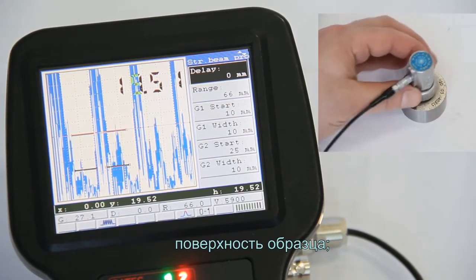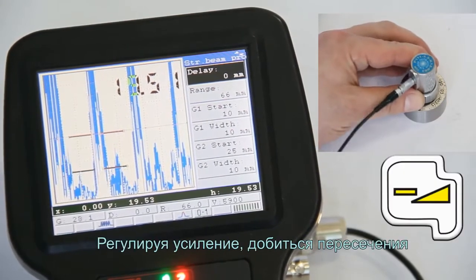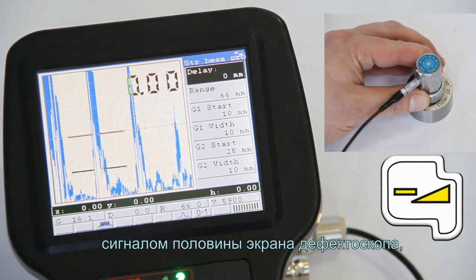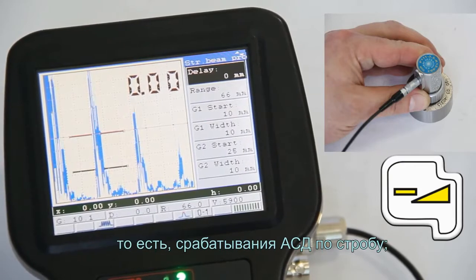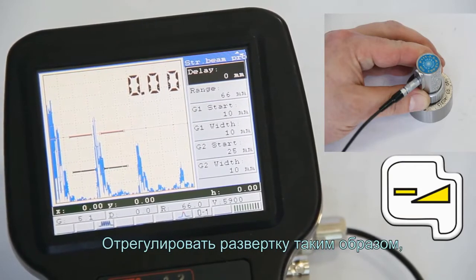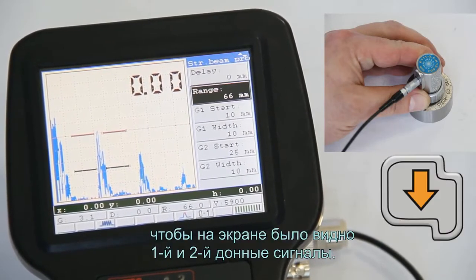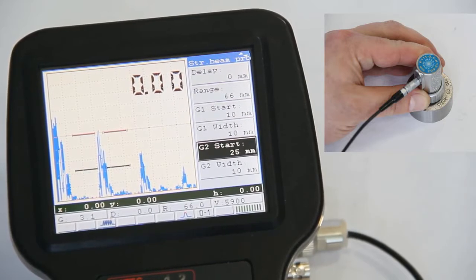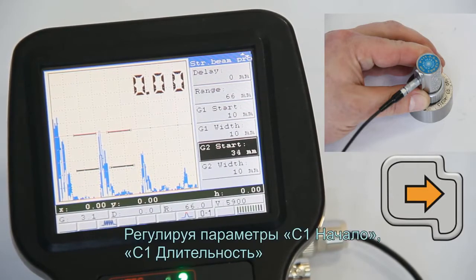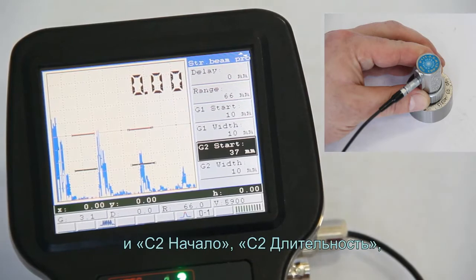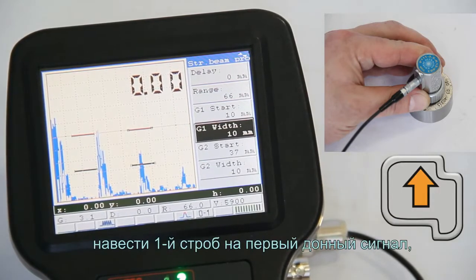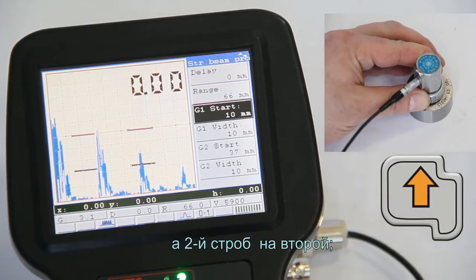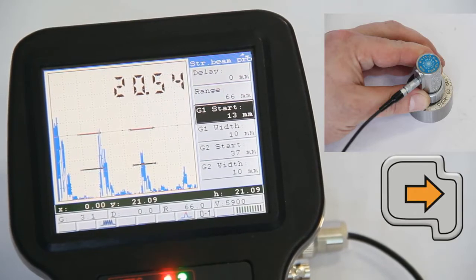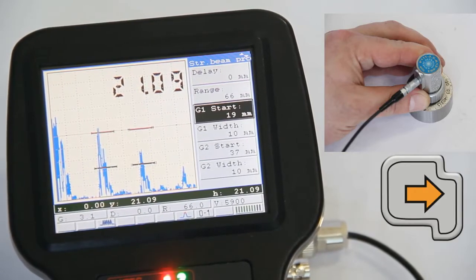By adjusting the gain, achieve the signal crossing 50% of the vertical scale of the screen, that is, alarm triggering. Adjust the scan in such a way that the screen shows the first and second back wall echoes. By adjusting parameters G1 start, G1 width and G2 start, G2 width, place the first gate on the first back wall echo and the second gate on the second back wall echo.